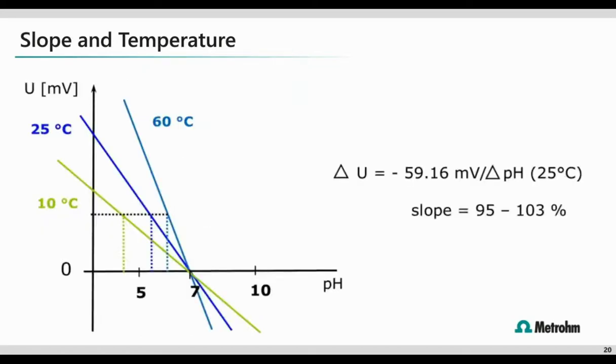However, if the electrode is used at a different temperature, the electrode slope will change and possibly the electrode 0 point. So on your screen now we see a sample. If you look at the blue line, the ideal sample measured at 25 C, if we take that same measurement and say it's chilled down, you can see the shift from either side there.